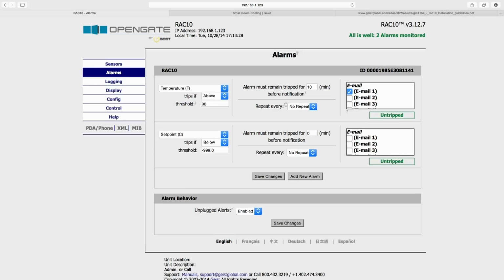You can set this to repeat, so you get a message every hour if the condition continues, letting you know what's going on. This is very useful. If you've got a lot of remote offices, you don't necessarily need to worry whether the server room temperature is 80, 81, 82, 85, or 86 degrees. But if it goes over 90 degrees, you know there's probably an issue, like the HVAC system failing. So these alerts let you know what's going on.